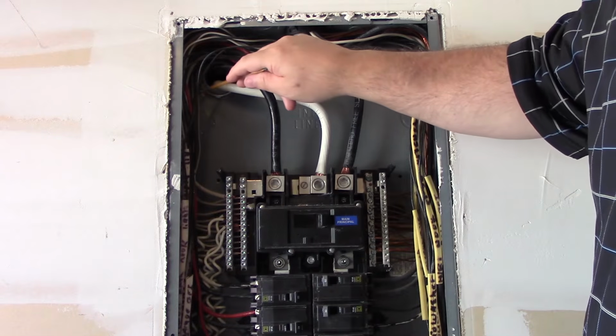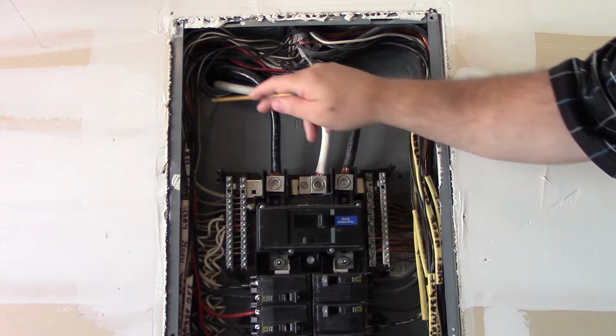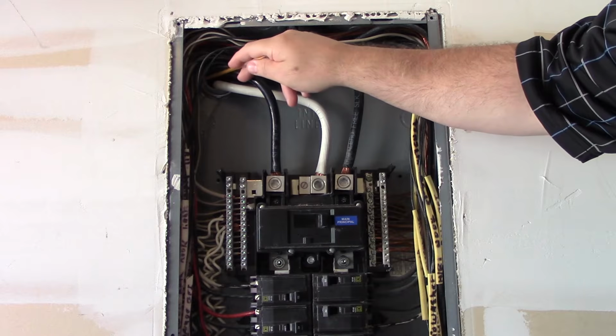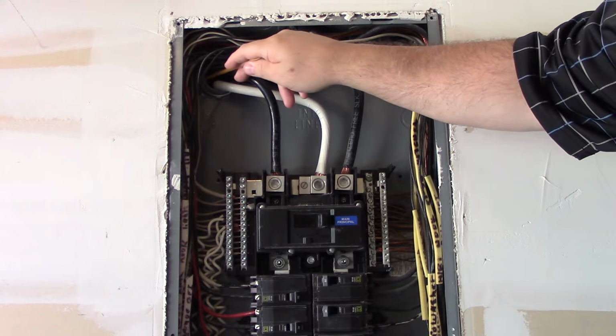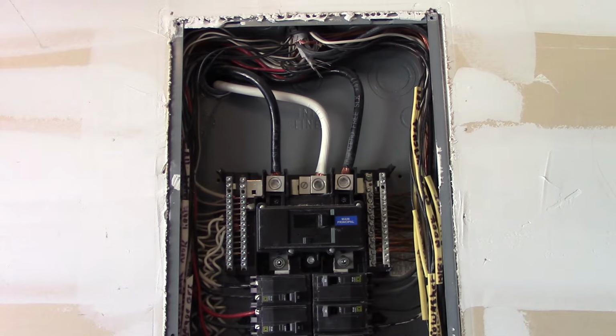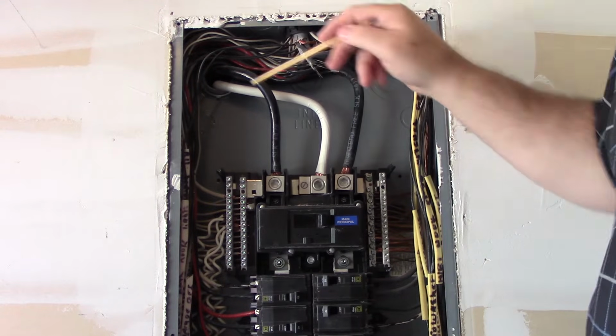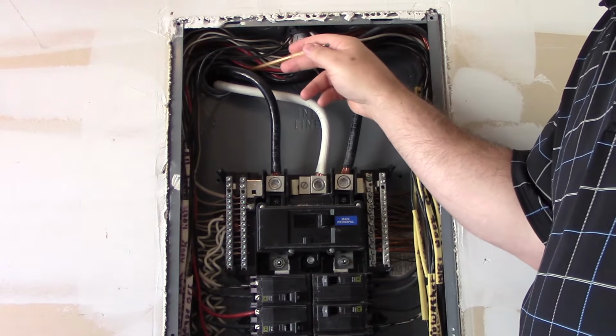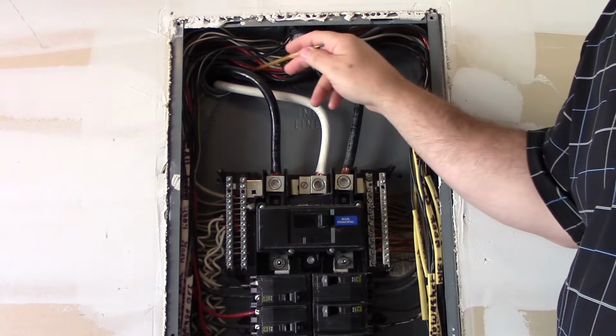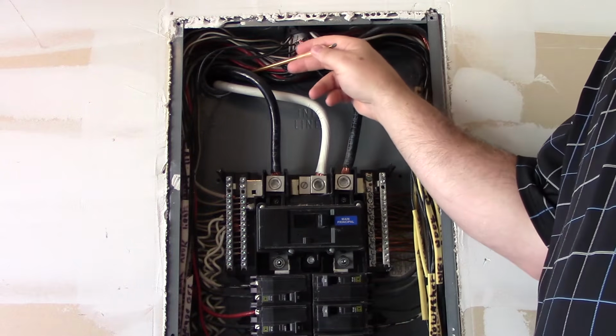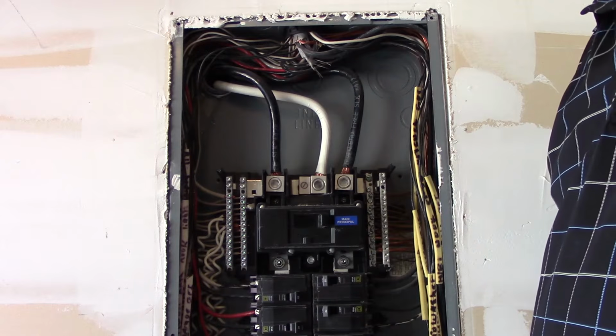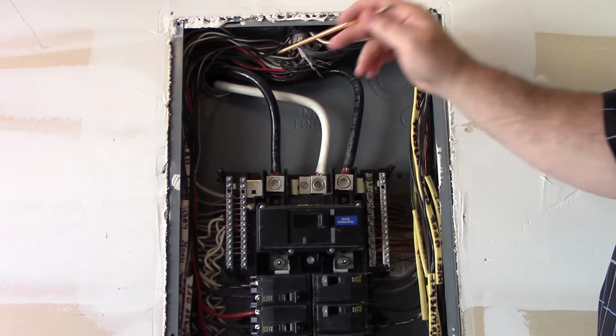Okay, so in this case, it's PVC. I do need a bushing on it, just to protect from damage as it comes in, so that adds that extra level of protection here. Now, as a municipal guy, if I see some damage in here, I'm probably going to call that out. If I don't see any damage and everything looks good and it's not bent too much, then I might not call it out, because they have to take all this loose in order to do that.